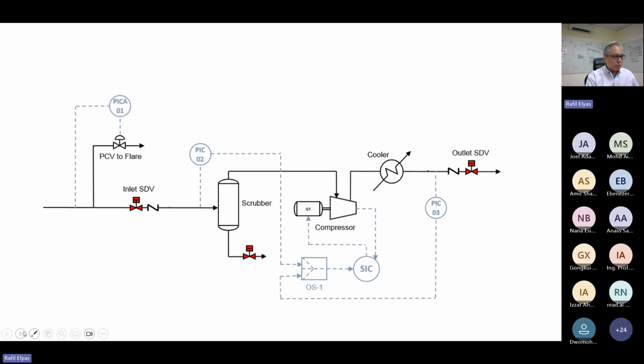So what do we mean by surge? Well, in some situations, you might find that the discharge pressure may go up. Why would it go up? Well, you could have a problem further downstream. Maybe this is feeding some other processing trains. Maybe some of the trains have tripped, and it has retarded the flow, causing the increased pressure over here. Could be that maybe there's an inadvertent closure of a valve.